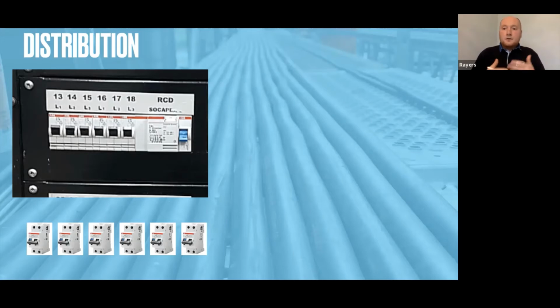So when specifying and looking at distribution, it's really important that for the vast majority of applications we use a row of RCBOs, as shown at the bottom. That way, in the event of an isolated fault on a circuit, you'd only lose that feed. In a real environment, losing the whole thing might mean losing your sound, lighting, or concession unit. It's very important to offer that segregation to make sure the show can continue to a greater extent.